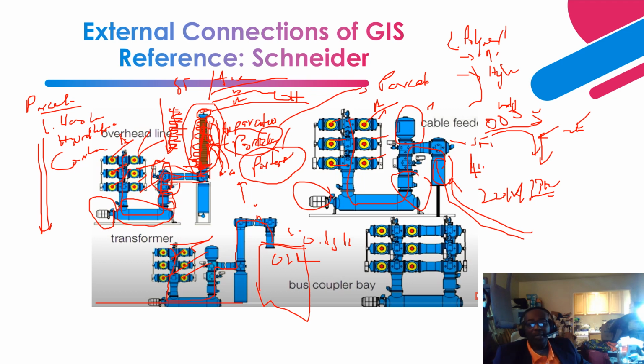Next is a bus coupler, right? Okay, so a bus coupler, like I indicated, right? If you have a double bus, right? Okay, then in between that, it's a breaker, a tie breaker, right? Okay, so the tie breaker is the one that couples these two buses together, right? We have bus A on this side, bus B on this side. We have bus A on this side, bus B on this side. So the tie breaker is what couples bus A to bus B, or bus 1 to bus 2, right?